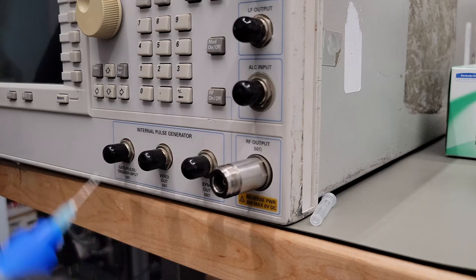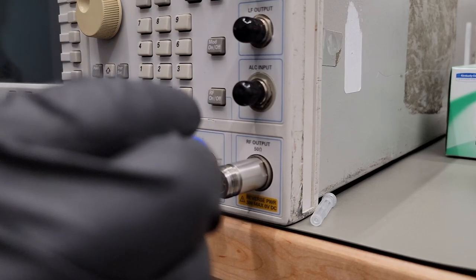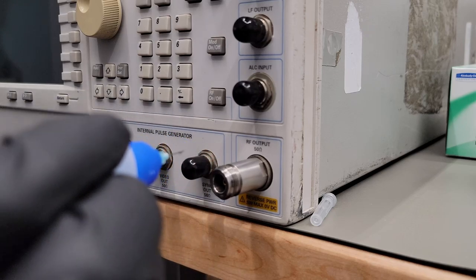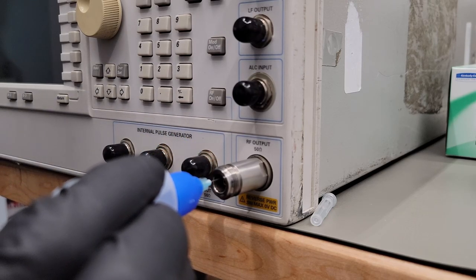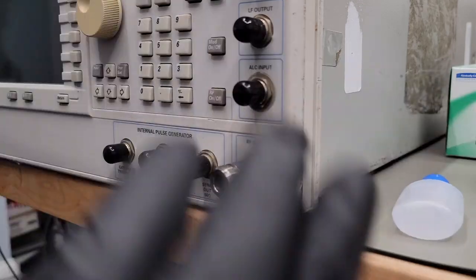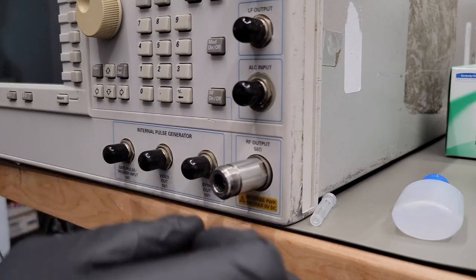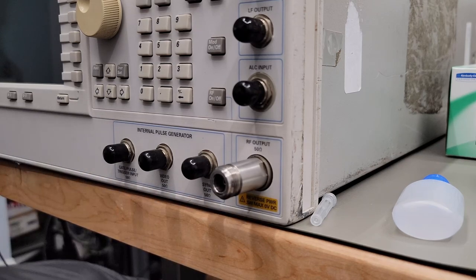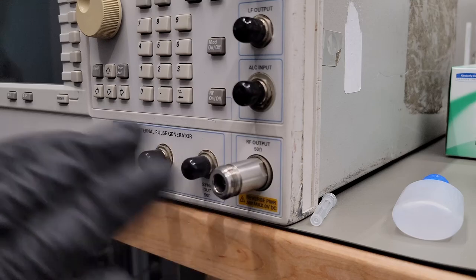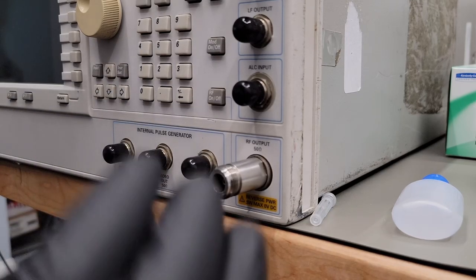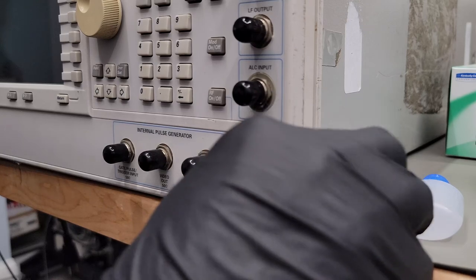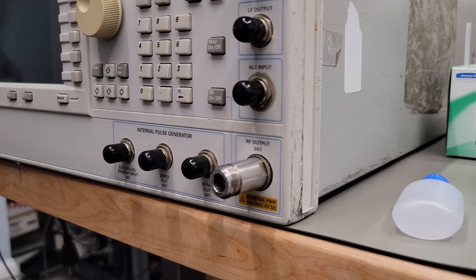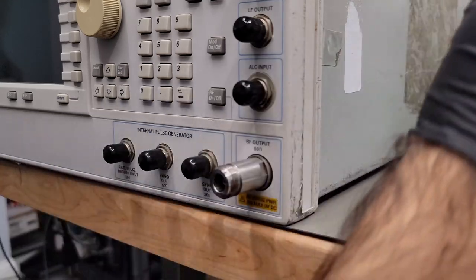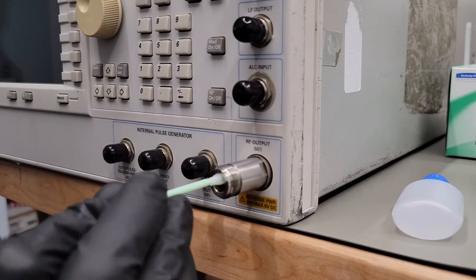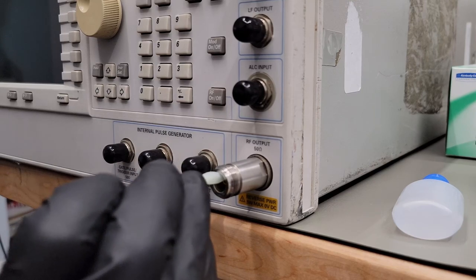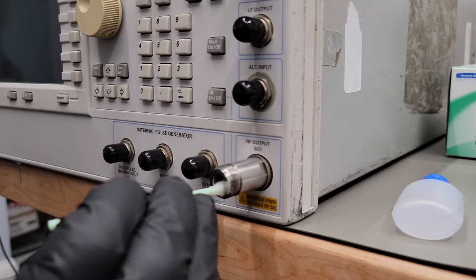So once I'm done swabbing there, I'll just apply some more alcohol on the outside, especially around the threads. Around the inside, drip some over the center conductor. Because notice that the male pin, when it goes into the female contact here, I have not actually swabbed or mechanically scrubbed that area. I've scrubbed everything else on the outside and the inside. So to clean that area, I suppose you could try using something mechanical to do it. I would not recommend that. I would just get the inside as clean as possible and make sure there's plenty of alcohol.